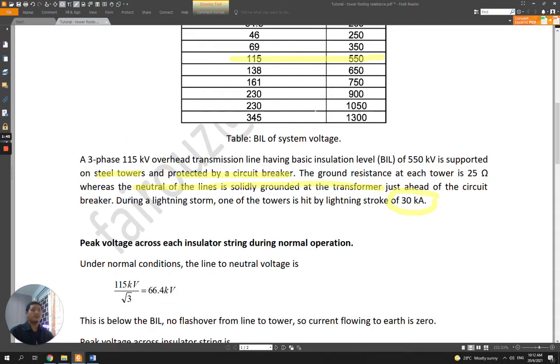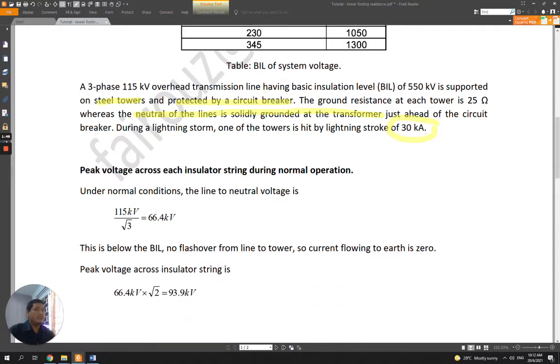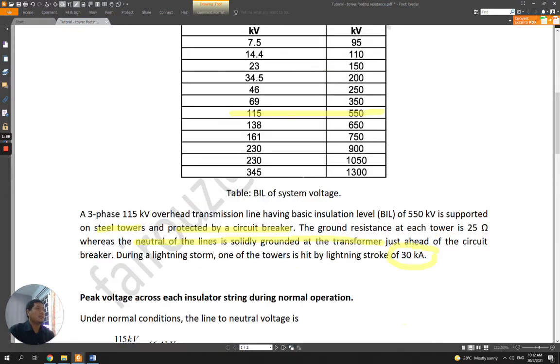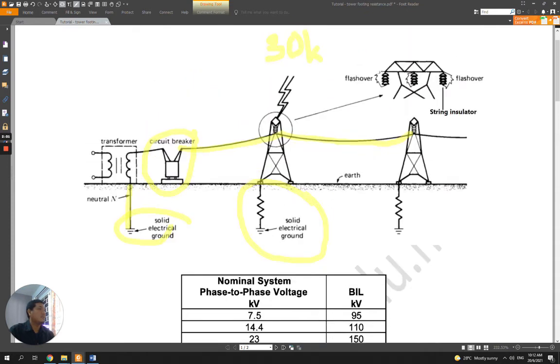So let's look at what happened before and during the lightning stroke. Alright, so peak voltage across each insulator string during normal operation. This is before the lightning strike. As you can see here, this is the string insulator. The bottom part of the string insulator is holding the line conductor, and the top part of the string insulator is hanging to the steel tower. So this part is grounded and this part is live, 115 kilovolt.